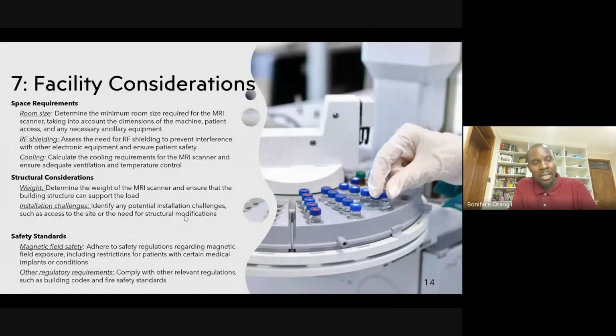But the good news is companies like Philips are coming up with helium-free magnets. Previously, some of the biggest factors driving the weight was the amount of liters of helium in the magnet. Now with the new innovations, we only take 7 liters in the magnet, which significantly reduces the weight of the MRI machine. And that is now allowing us more capability to install it on the first floor, second floor, third floor, depending on where you are.